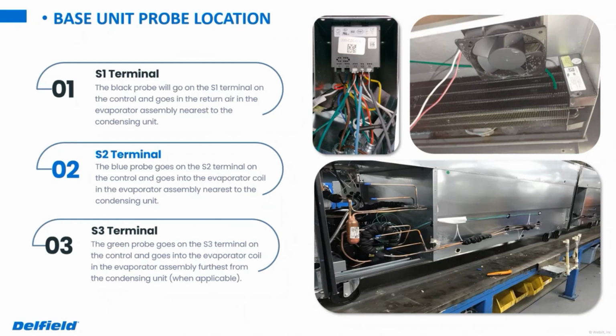So basically, as a rule of thumb, you're going to have a black and a blue probe. On the occasion that you do have a second evaporator, there would be a green probe. Your black probe is your return air probe that goes into the return air of the evaporator. Blue is your first coil probe, and that gets buried into the coil. And they have the optional green probe. That would be if you had, like on this low boy here, two evaporators. If you have a second evaporator, that would be where your green probe would go.